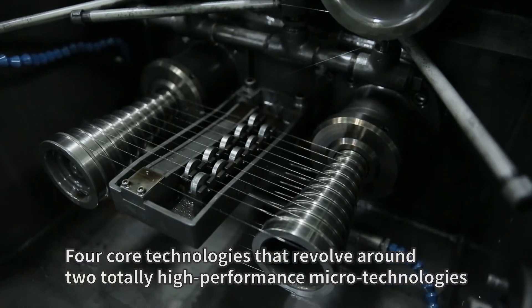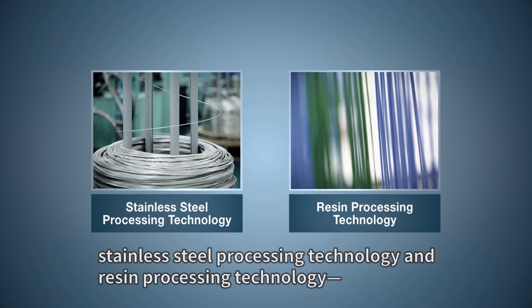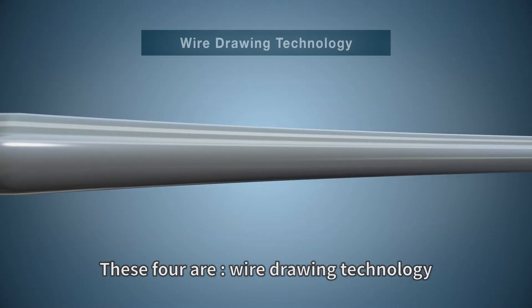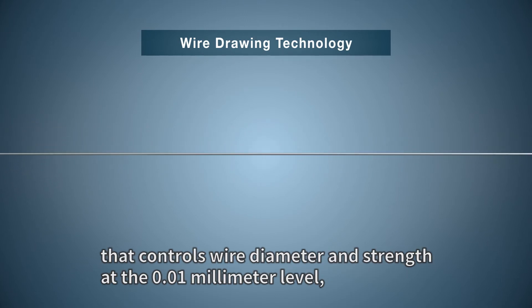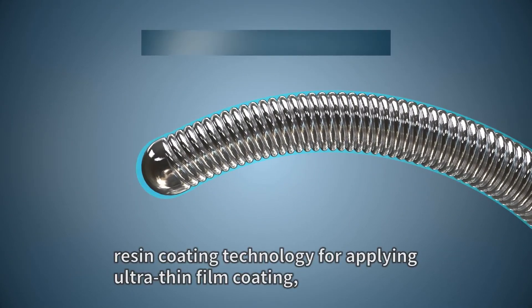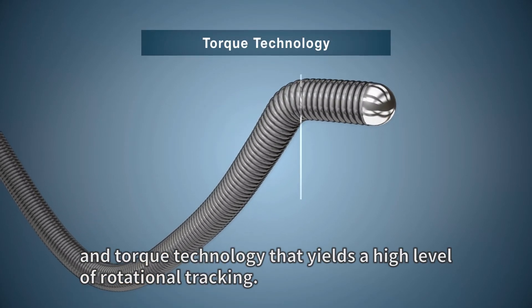Four core technologies that revolve around two high-performance microtechnologies — stainless steel processing technology and resin processing technology — form the foundations for Asahi Intecc's unique solutions. These four are: wire drawing technology that controls wire diameter and strength at the 0.01 mm level; wire forming technology that enables formation at the micron level; resin coating technology for applying ultra-thin film coating; and torque technology that yields a high level of rotational tracking.